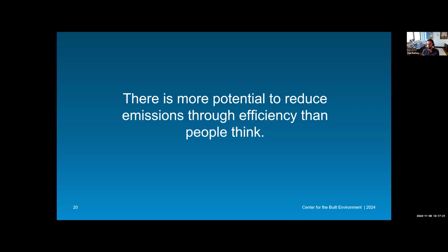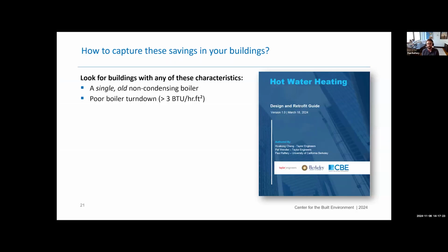So if you're working on buildings or you're managing people who are working on buildings, we have a design and retrofit guide that was one of the outputs of this project. You can screen very quickly for good candidates for some of these measures by looking for buildings that have any of these characteristics. If you've got a single old non-condensing boiler or a boiler plant with poor turndown serving a building, that's a great candidate.